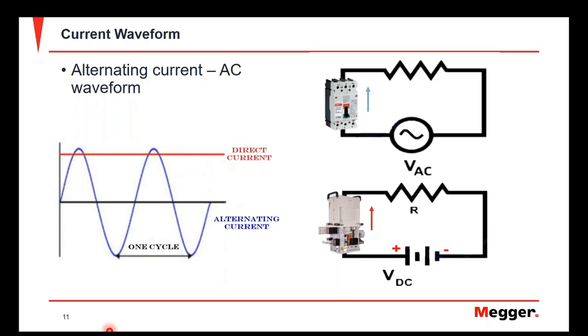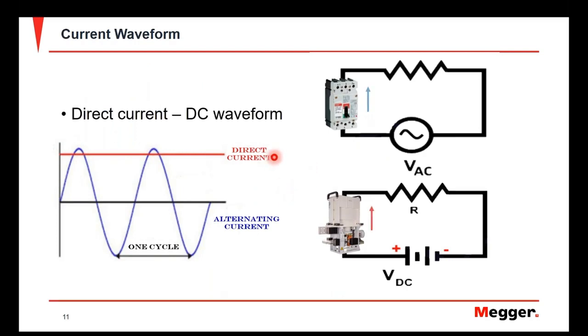Another thing to consider is the waveform used when doing primary current injection tests, because different circuit breakers require different waveforms, and we have different instruments that provide different outputs to satisfy these requirements. Typically for an AC waveform we use an AC current source for a standard molded-case circuit breaker, but we also use a DC waveform for certain types such as high-speed DC circuit breakers used in railway infrastructure or DC vehicular applications.